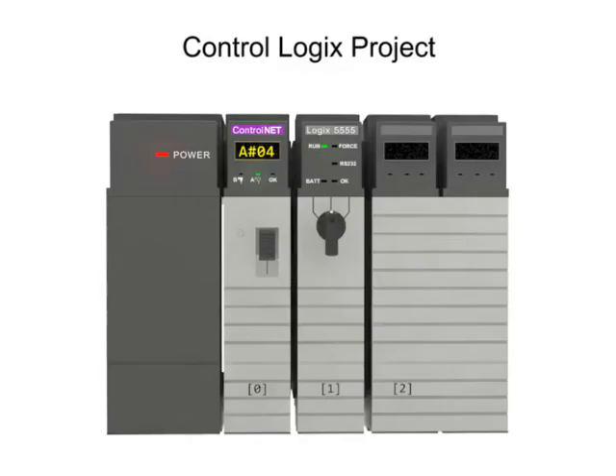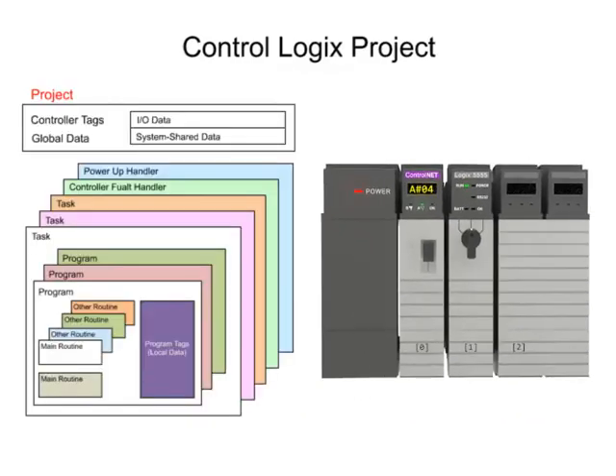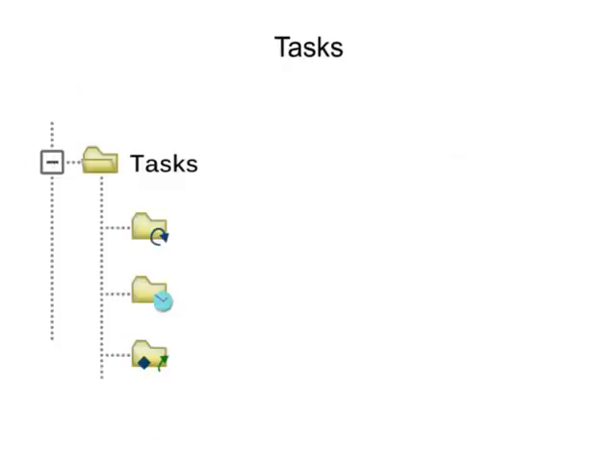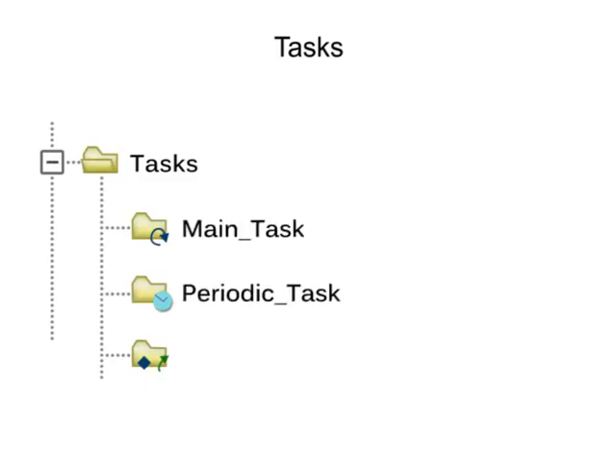A ControlLogix project is comprised of tasks that contain programs, routines, and other elements. Tasks within the project set the execution priority for one or more programs and schedule the program's execution.